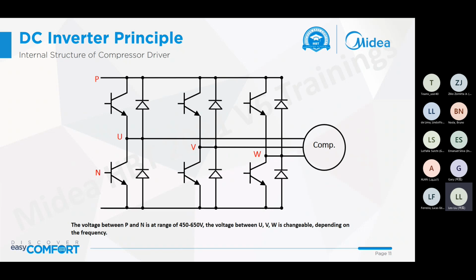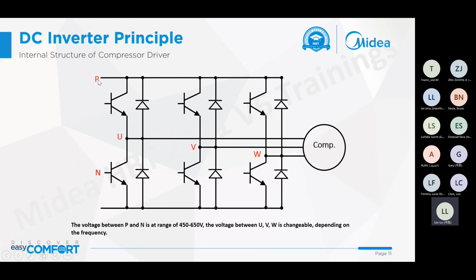Okay, so we can see the inner structure of the compressor driver. Power supply, three-phase, the voltage between the terminal P and N is in the range of 450 to 650 voltage. And the power supply of the compressor, UVW terminals, can be adjustable, so changeable. So after frequency changed, the voltage also changed. So different frequency, different voltage, so we got the different capacity for inverter compressor.